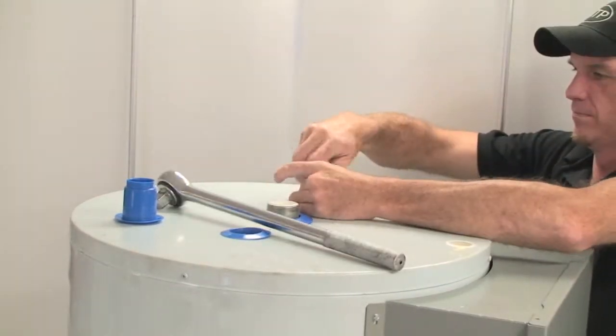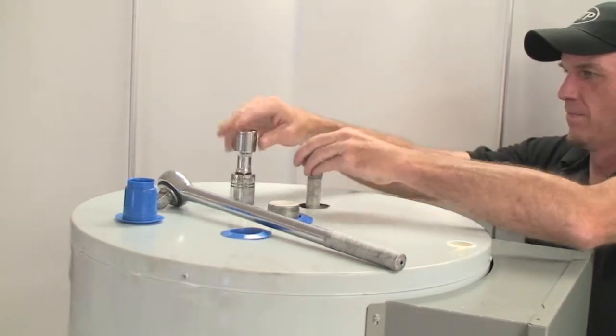Keep in mind a breaker bar may be needed to remove anode rod and you must assure tank stays in place and does not rotate as this could cause further damage. Inspect anode rod and replace as necessary.